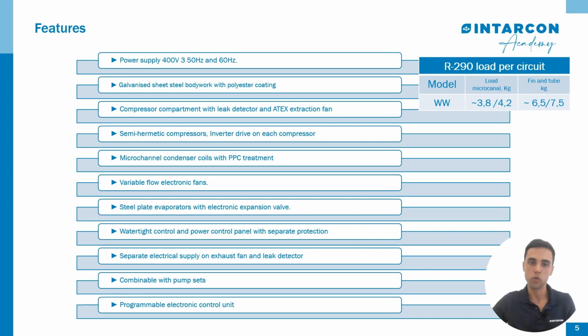The main features are power supply, 400 volt 3 phases, 50 or 60 hertz, galvanized sheet steel bodywork with polyester coating, compressor compartment with leak detector and ATEX extraction fan, semi-hermetic compressor with the use of VFD, microchannel condenser coils with polyester powder coating treatment, variable flow electronic fans, steel plate evaporators with electronic expansion valve, watertight control and power control panel with separate protection, the use of a separate electrical supply on exhaust fan and leak detector in case of failure of the main power supply, and it's also combinable with pump sets that are manufactured here in INTARCON too. Finally, we use a programmable electronic control unit here.